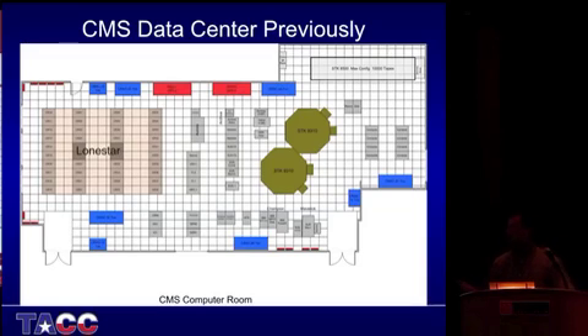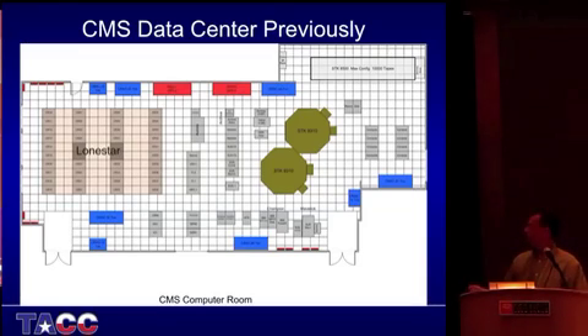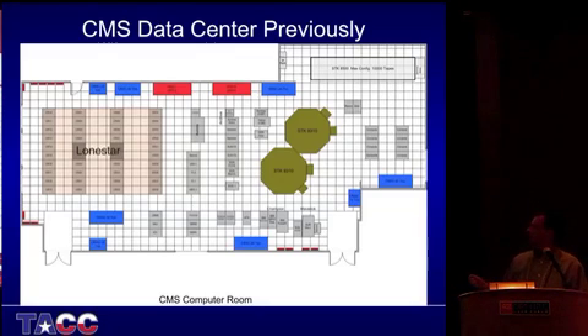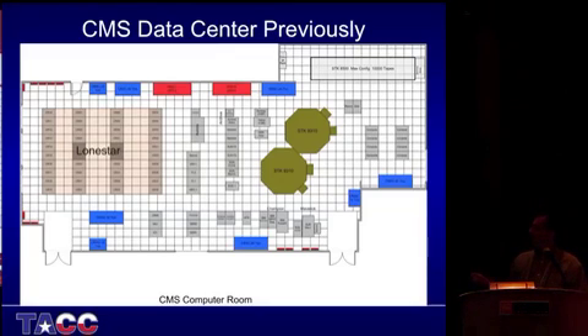What we did is, and we made some design decisions here for the system: if you notice, we have 4 rows. The equipment is much more spread out. And this is because we actually have a higher power density per rack, and we needed to increase the volume of air around in the various rows.